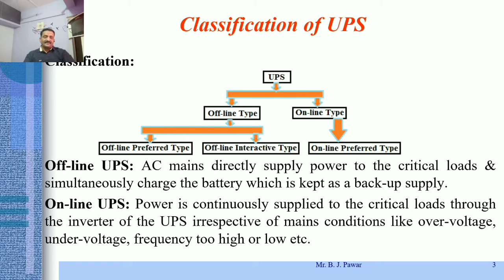While in the case of online UPS, power is continuously supplied to the critical load through the inverter of the UPS, irrespective of the mains conditions like over voltage, under voltage, frequency too high or too low, etc. So whatever the condition of the AC mains, the load always gets power through the inverter in this online UPS. While in the case of offline UPS, what happens? Whenever there is a power failure or power conditions are not good, then the inverter gets activated. Otherwise, the load is directly powered through the supply mains. So basically, this is the basic difference between offline and online.